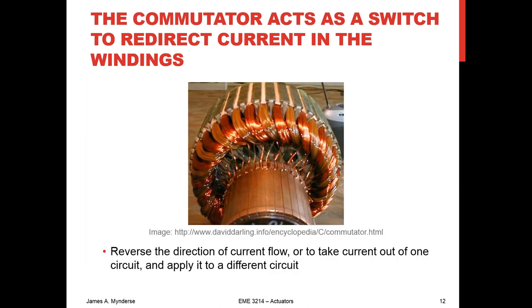How does the commutator actually work? It acts as a mechanical switch — instead of a transistor, which is an electrical switch. It allows the brushes to make contact with different elements on the outside, giving different current flows. In wave winding there are two paths the current can take. As the commutator rotates relative to the brushes, different contacts make contact with the brushes at any given time. That gives a path for current from one brush through all the windings out to the other brush. As it rotates, it reverses the direction — back and forth — which continuously rotates the motor.